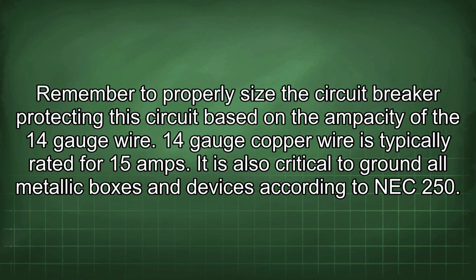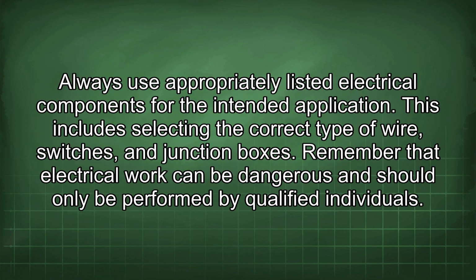Remember to properly size the circuit breaker, protecting the circuit based on the ampacity of the 14-gauge wire. 14-gauge copper wire is typically rated for 15 amps. It is also critical to ground all metallic boxes and devices according to NEC 250. Always use appropriately listed electrical components for the intended application. This includes selecting the correct type of wire, switches, and junction boxes.